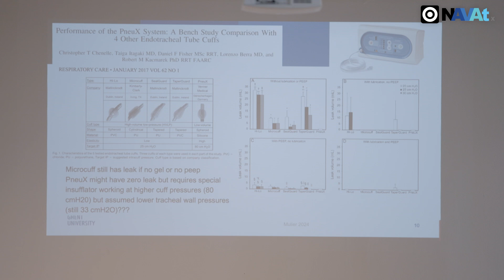And one day I opened the water pump of a bicycle pump, and look here, what is this valve doing? This is actually a cup, and you can move the cup down without any pressure, and when you bring it up, it closes. And the higher the pressure you generate, the better it closes off. Now, we should make a cuff in the same way, but it's not moving in the trachea, it's still. So we should have a cup that is a little bit like such a water pump. And the higher the pressures here in the lungs, the more it presses the cuff against the tracheal wall. And then you don't need high pressures in the cuff. You can even have pressures in the cuff below 25 centimeters of water.